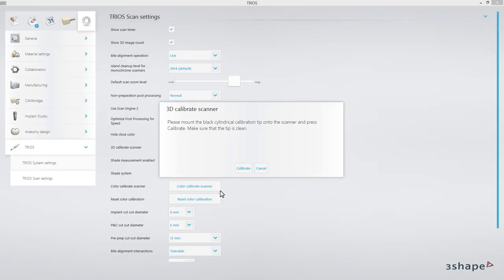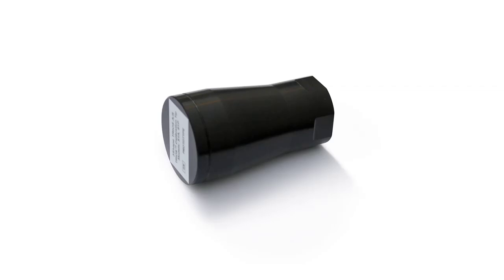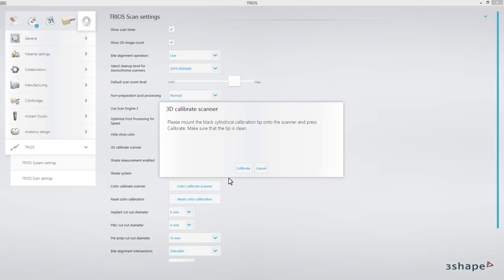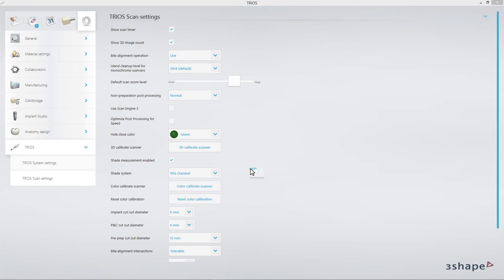Before proceeding, make sure that the front glass on the scanner, as well as the inner side of calibration tip, are clean and free of dust or scratches. Mount the tip and proceed with calibration. It will take up to 1 minute. When it is finished, remember to remove the 3D calibration tip from the scanner in order to prevent it overheating. As soon as 3D calibration is completed, you can proceed with color calibration.